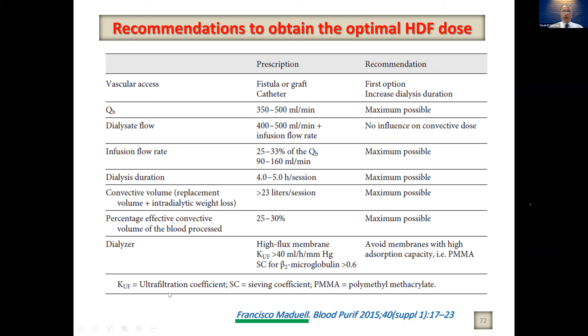Convective volume, replacement volume plus the intradialytic loss, more than 23 liters per session, maximum possible. Percentage effective convective volume of the blood processed 25 to 30%, maximum possible. Dialyzer, high flux membrane with ultrafiltration coefficient more than 40 ml per hour per millimeter mercury with SC for beta 2 microglobulin more than 0.6. Avoid membrane with high adsorption capacity.